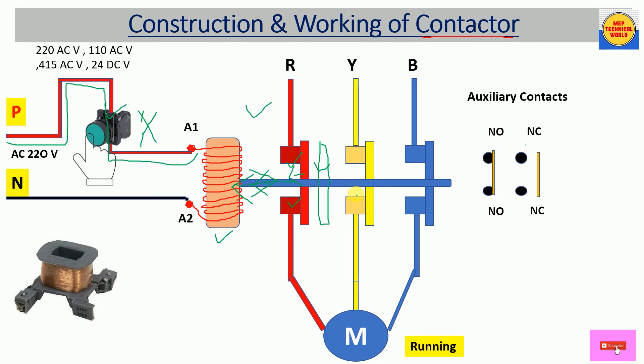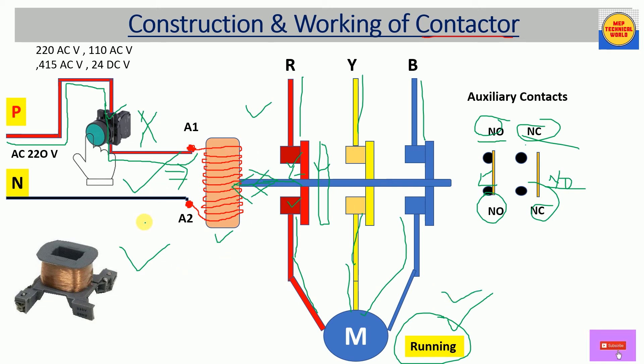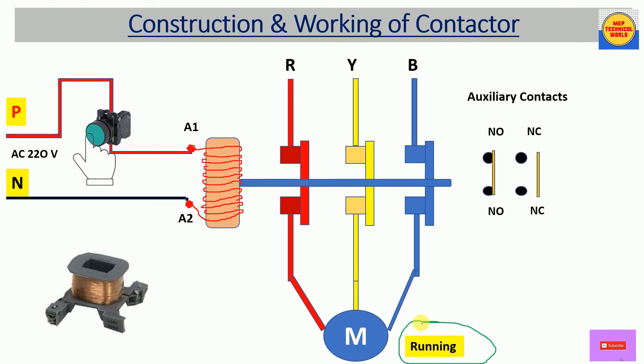At the same time, the auxiliary contacts also change state — the normally open becomes normally closed and the normally closed becomes normally open. In this condition the contactor allows the three-phase power to flow to the output side and the motor reaches running condition, because we are still pressing the normally open push button and still giving power supply to the contactor coil. We haven't implemented a holding or latching circuit yet — that will be discussed in the next video.